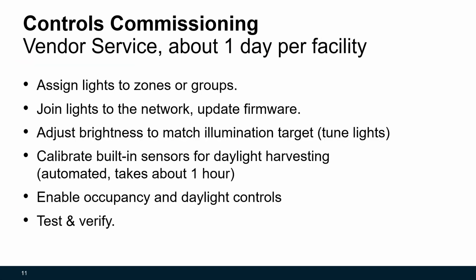The commissioning step was done by the vendor and took about 1 day per facility. This was completed by the lighting vendor for a fee as part of their standard service offering. During the commissioning activity, they assigned lights to the zones or groups, joined the lights to the network, adjusted the brightness settings to the desired settings, calibrated the built-in sensors for daylight harvesting, and enabled the occupancy and daylight controls. Finally, we tested and verified the operation, and the lights were ready to use. Importantly, if you ever decide that the controls are not working out, you can completely disable the controls and use the LEDs as ordinary lights with the light switches or circuit breakers that you already have.